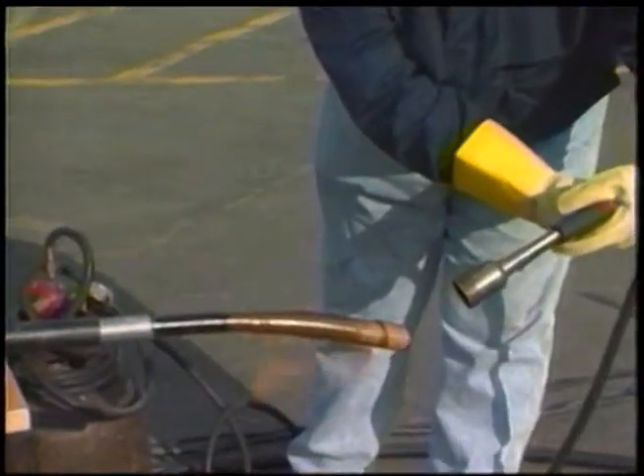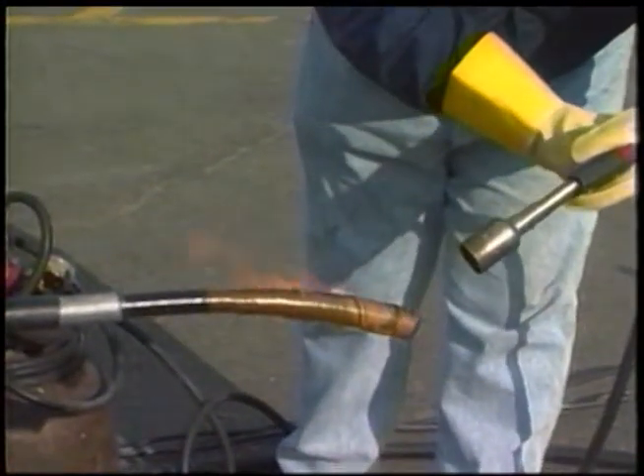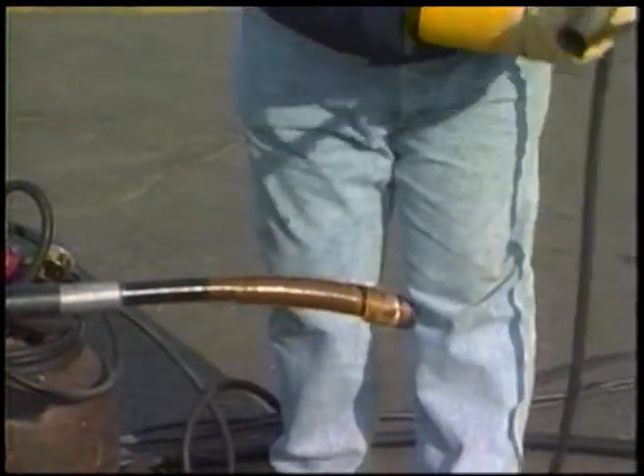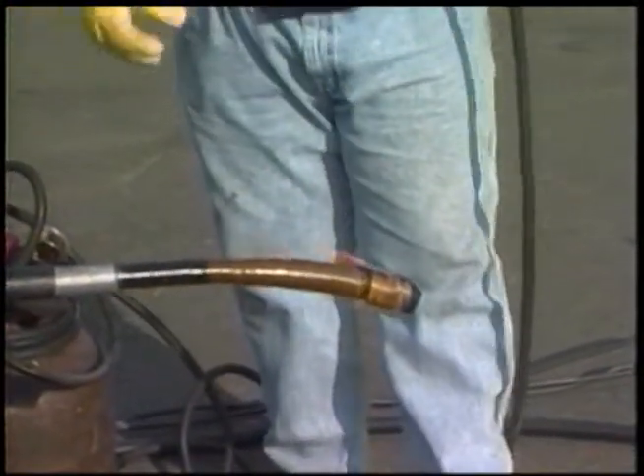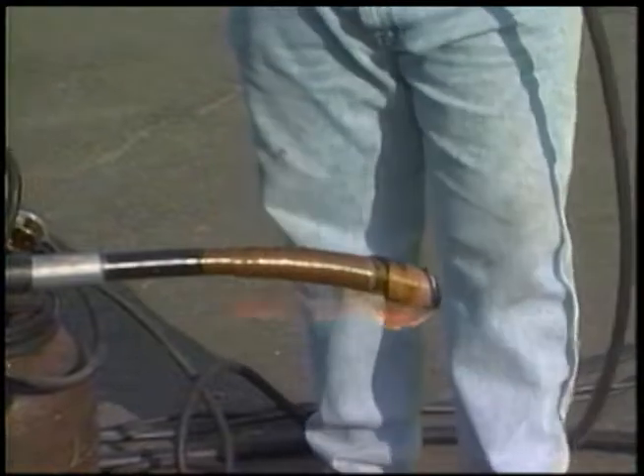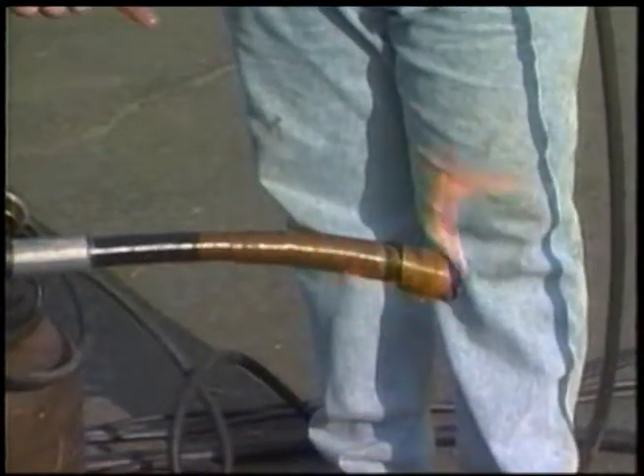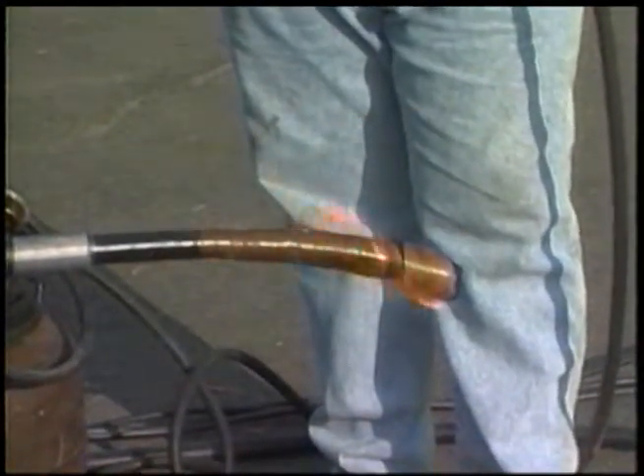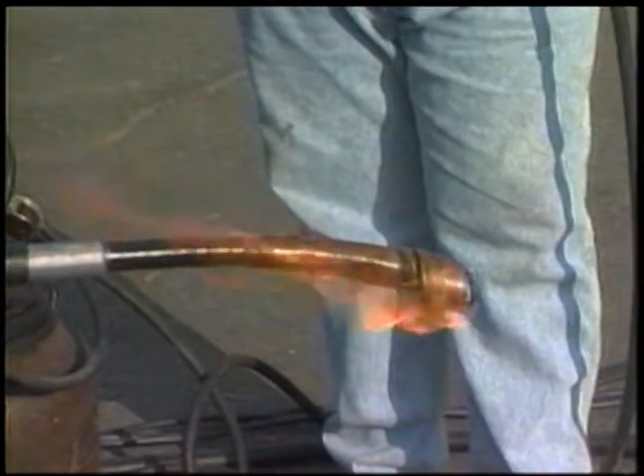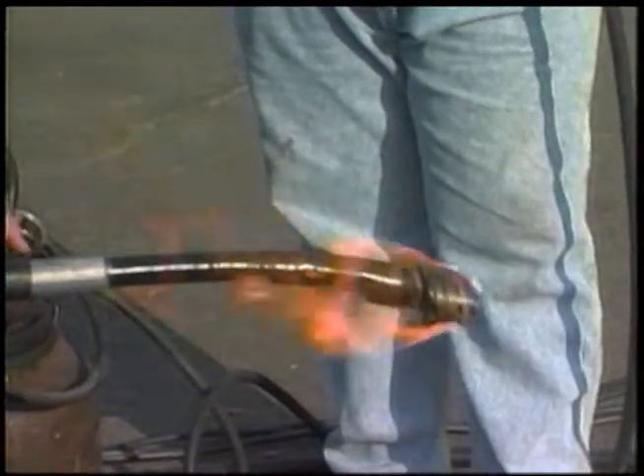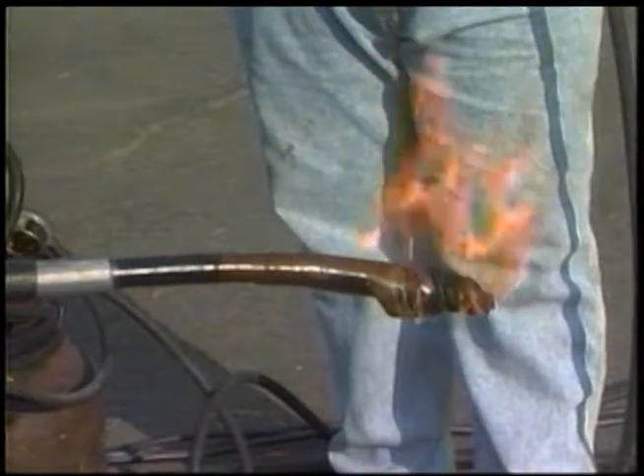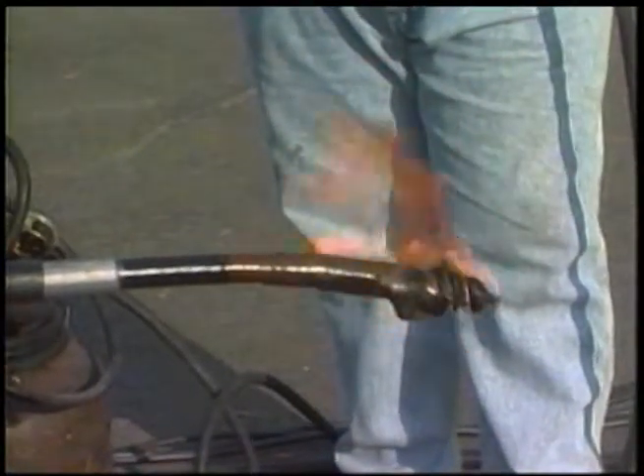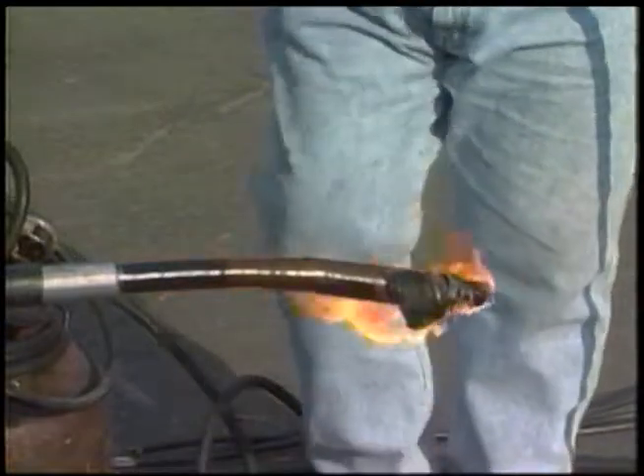Okay, that looks good, Kurt. Looks like it's going to go by itself. I think we can take it off now. Now, as you can see, the paper tapes and the oil saturated, it wants to continue to burn. As it continues to burn and burns its way back, it'll eventually come to the point where it melts the lead and the fire goes continuously from manhole to manhole. Okay, Kurt, I think we can put it out now.